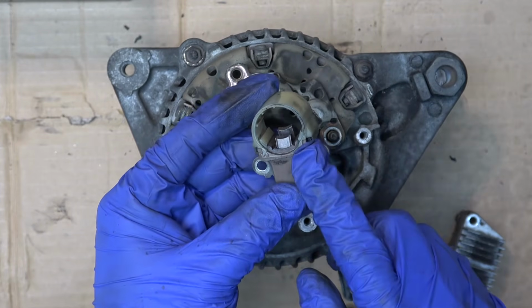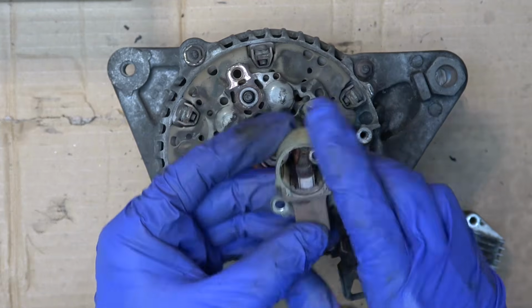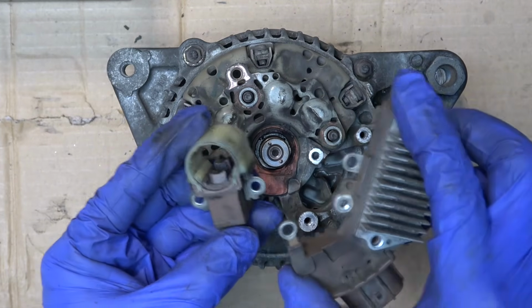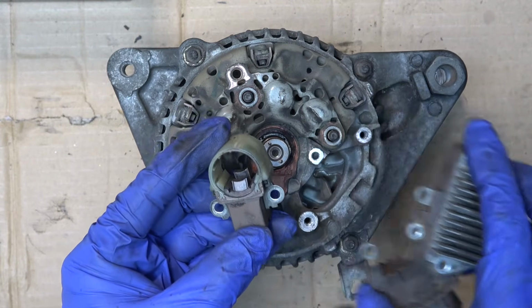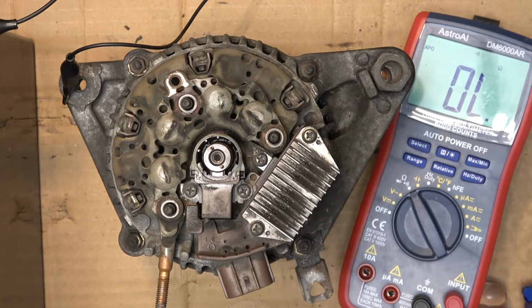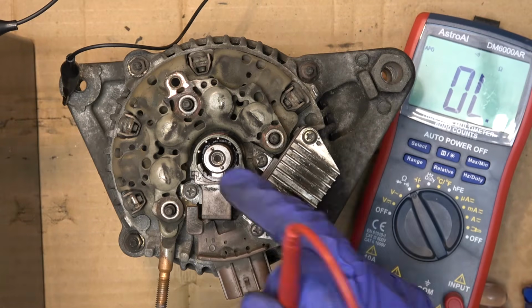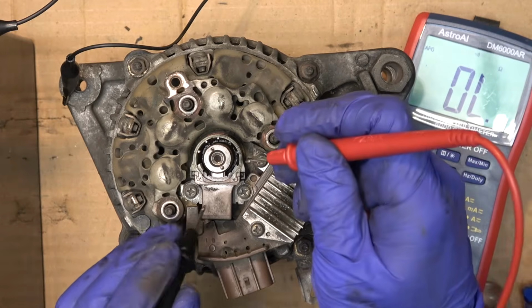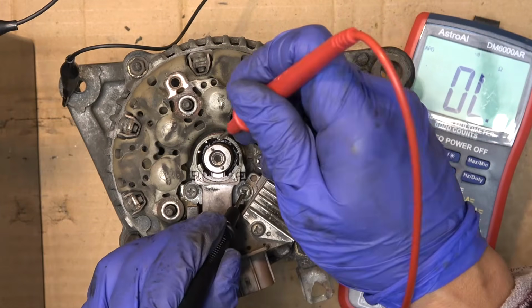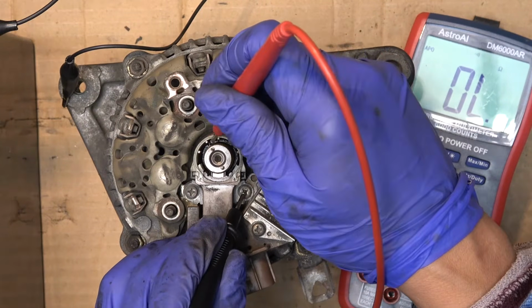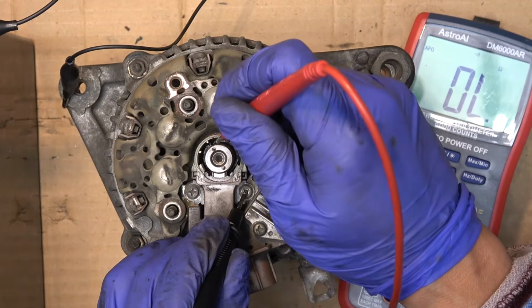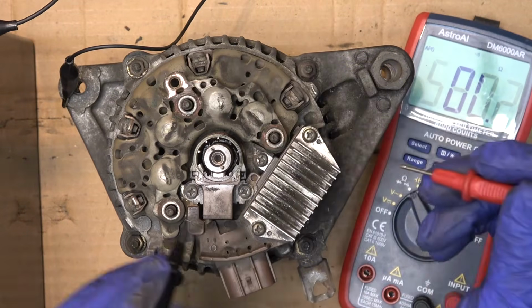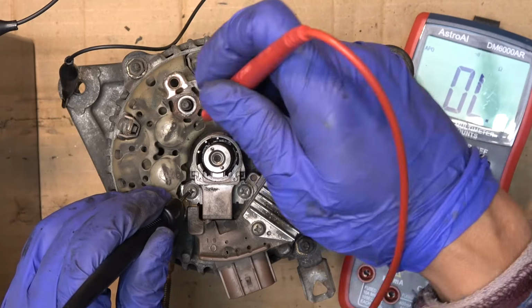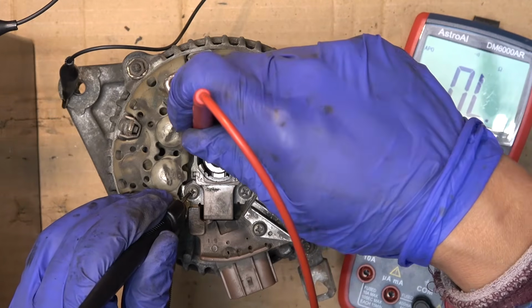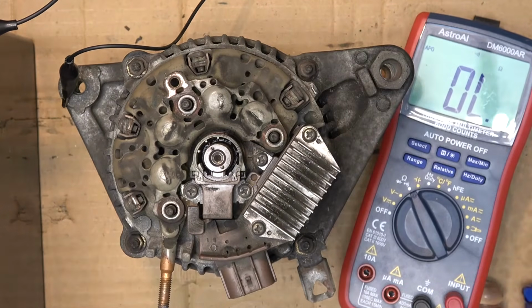Let me go ahead and put this new set of brushes in, and I'll do a test again to see if it works. But first, let's try and do a continuity test with my new set of brushes. This here with the top slip ring, there we go, it's touching, therefore it's beeping. This one should go to the bottom slip ring, there we go, so it's working.